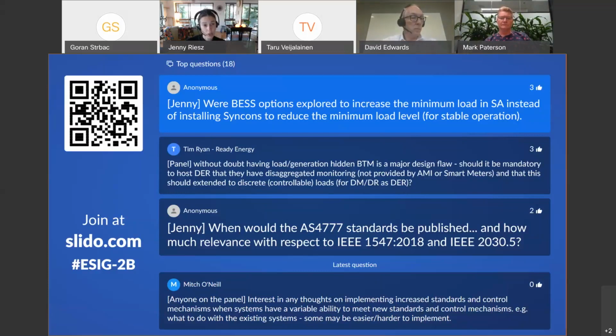If you tried to use batteries just as a solar soak to lift load, they can typically only absorb like that for an hour or two given their design, then they're completely full. During the middle of the day we need them to last 6 to 8 hours, so it would be very expensive to build enough batteries to soak up all that solar. A much cheaper option is to have PV capacity able to be turned down in those rare periods when necessary.